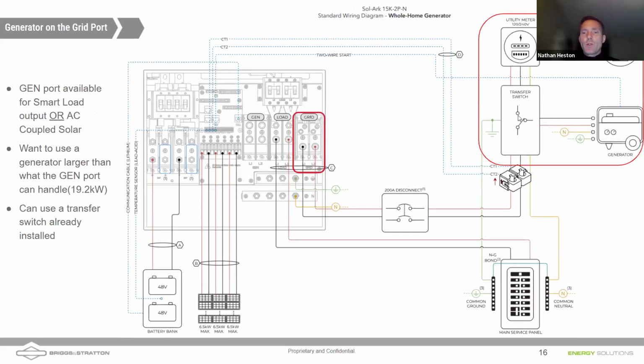The generator is coming through a transfer switch here, and that would give you the ability to bring in a larger generator. The generator port on the Sol-Ark 15k is fused at 100 amps. It's an 80 amp continuous port, so 19.2 kilowatts. So if you want to bring in a larger generator, like a 26K, you certainly could connect a larger generator to the gen port, but you would have to derate it down to 19.2 kilowatts.